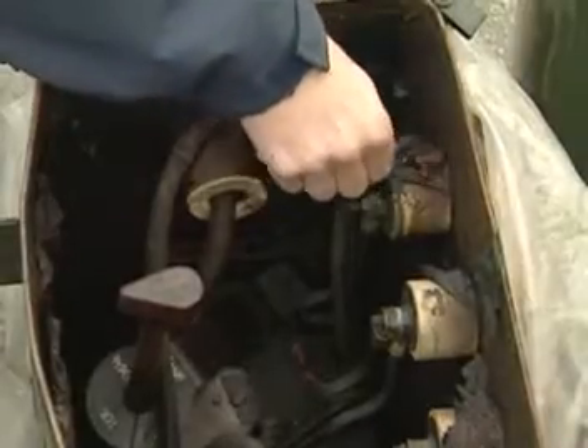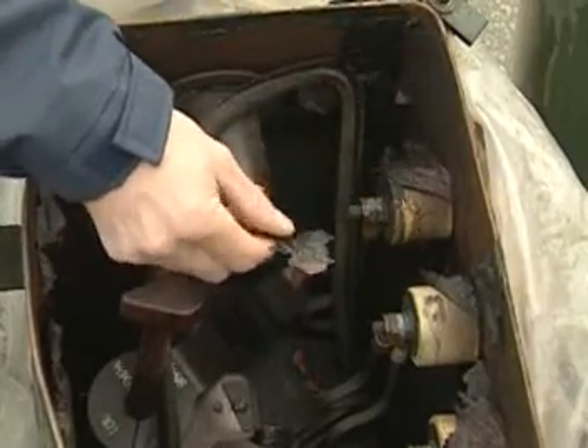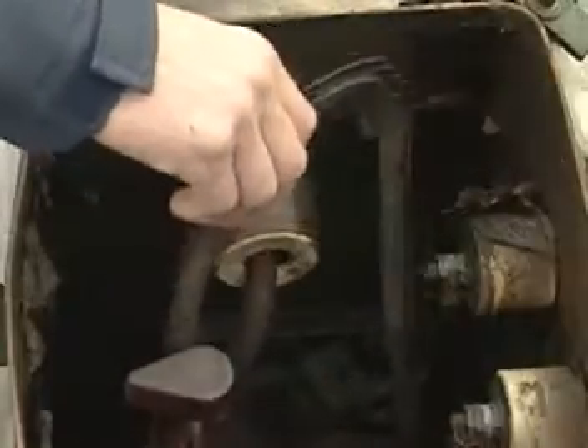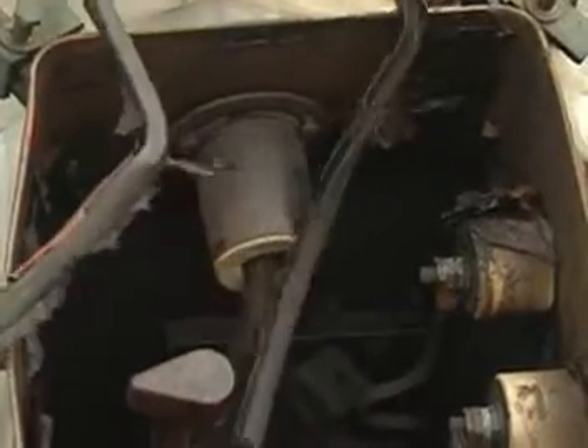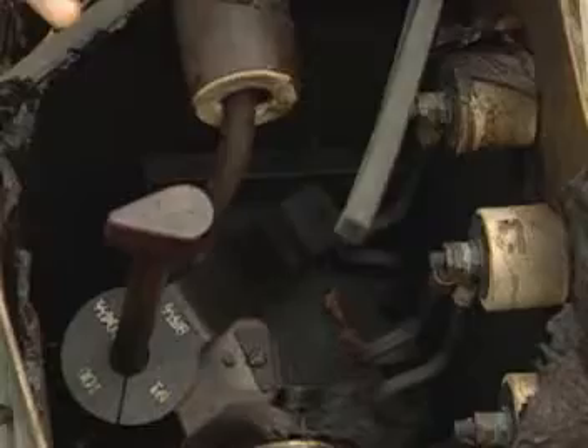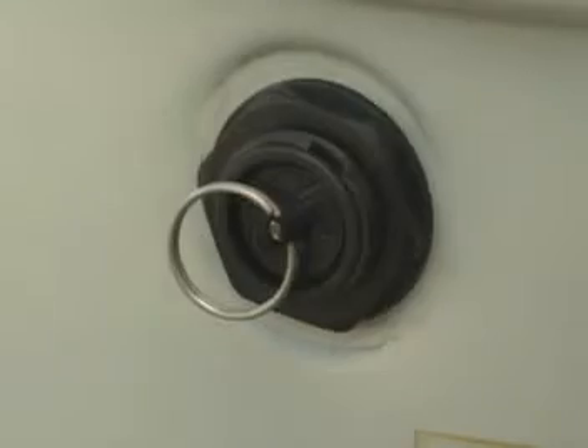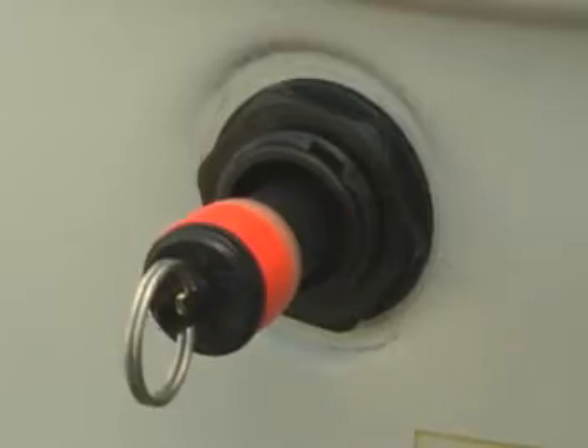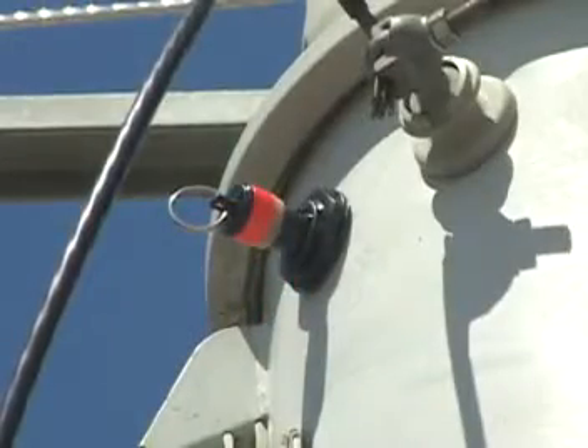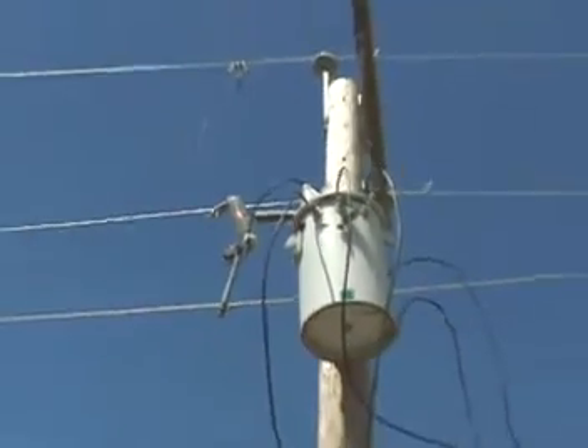If the internal fault is undetected and the transformer is re-energized, the risk of explosion increases due to the resultant contamination in the oil. To efficiently identify faulted transformers and avoid their re-energization, IFD Corporation has developed a device called the Internal Fault Detector, or IFD.